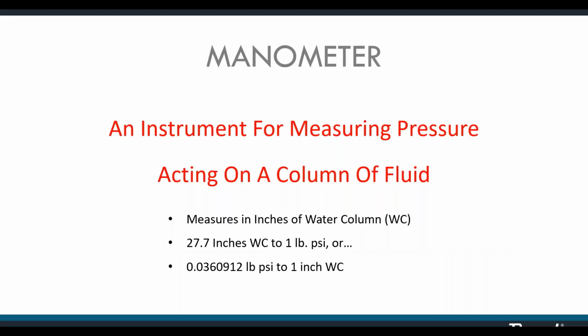If you plan to install or work on a gas burning pool heater, you should have a manometer. This device measures pressure acting upon a column of water. The increments are in inches of water column, and there's just under 28 inches of water column to 1 pound PSI. Okay, so we're only talking about small amounts of pressure here. That pressure is just there to drive the volume of gas.